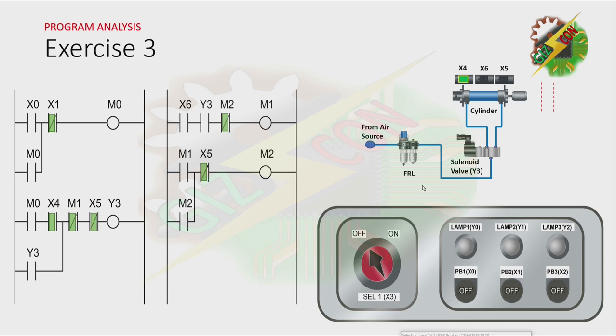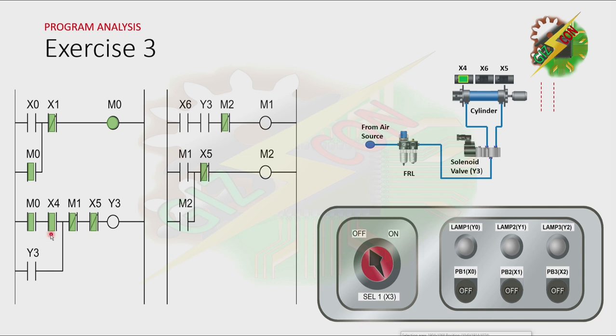This will be my answer to this problem. Let's press PB1. By pressing PB1, M0 will be energized. And because there is a latching here, M0 will not turn off even if X0 is not energized anymore. And because M0 is energized and the cylinder is at fully retracted position, Y3 will turn on. That will cause the cylinder to extend.